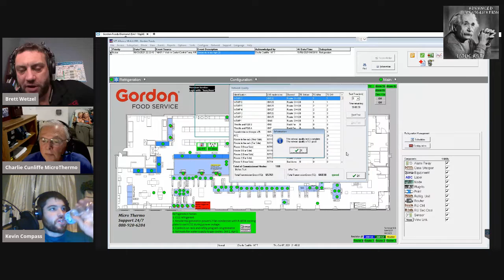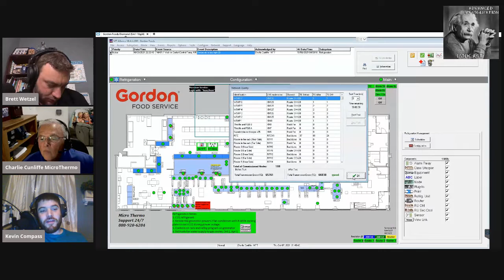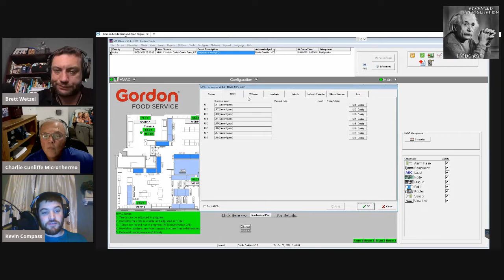What were the numbers before and after, Kev? To be honest, I didn't really check. I just knew that was the last part of the job, and as soon as we brought the HVAC online, it was nothing but problems. I didn't check at that point because we already knew there was an issue once we saw the daisy chains. So right away we knew we had to start moving a bunch of them around. We ended up starring a couple, and it got a lot better after we made a couple of stars and got rid of the big part of the daisy chain at the front of the store.